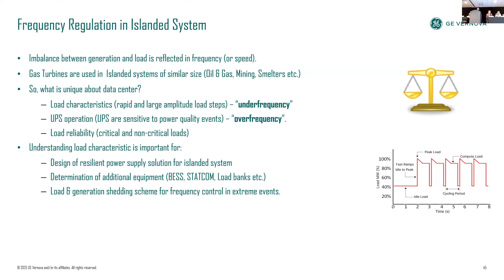and that should be considered when we design such systems, right? And also there are other considerations due to load loss whenever the UPS in the data center trips or picks up the load, causing a significant load rejection event, causing overfrequency. So in an islanded system with data center load, we expect to see both issues, one with overfrequency and the other with underfrequency, and the solutions, whether hardware or operational, would account for both of these issues.